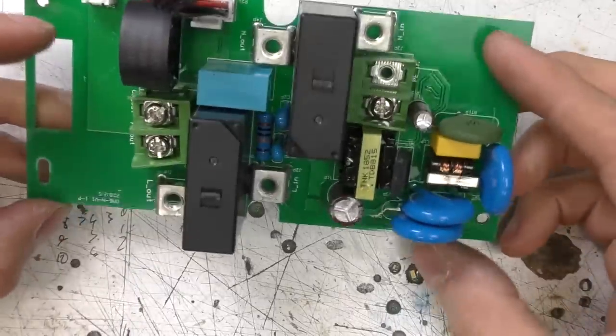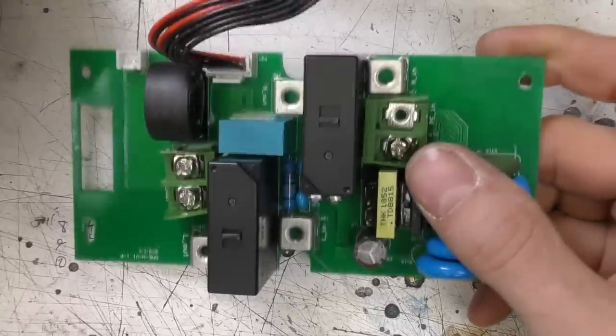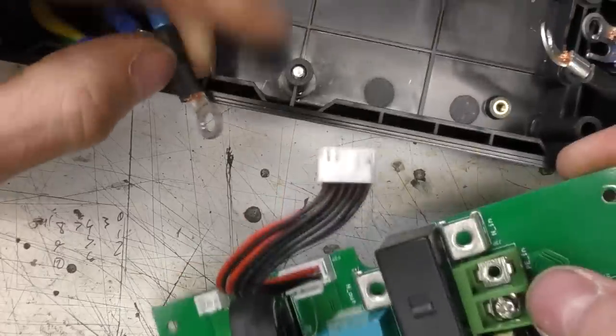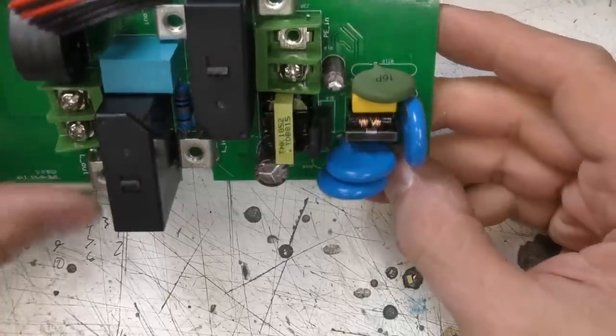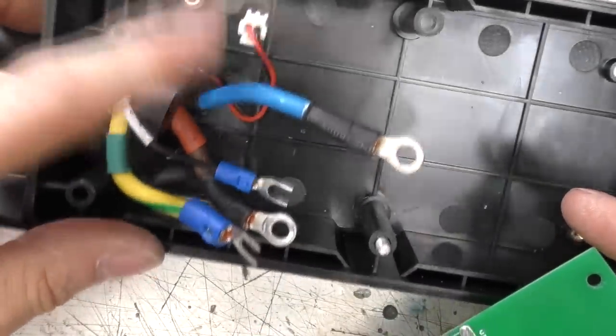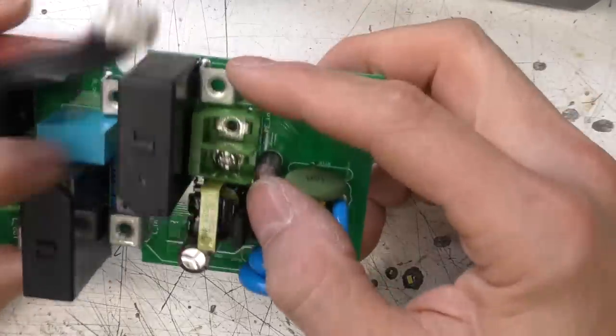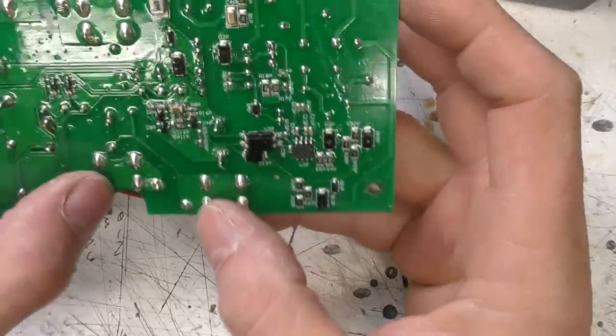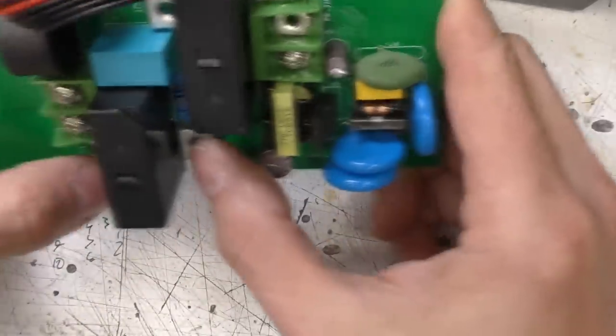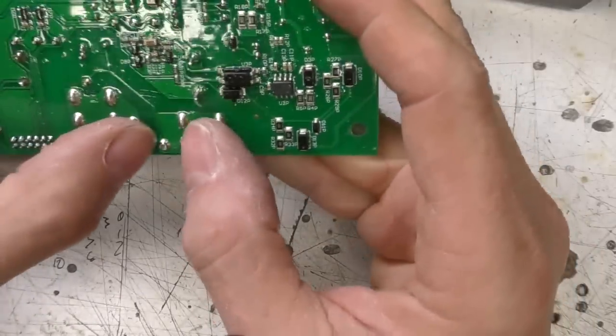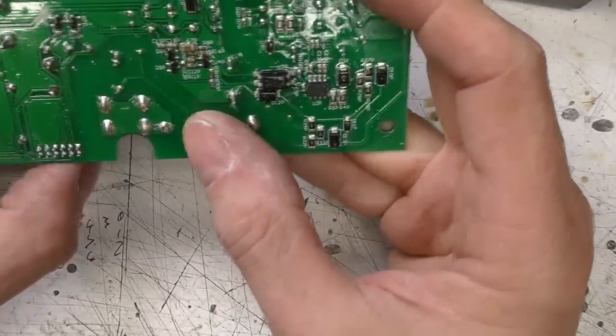So this board comes out much easier than the other unit. The neutral wire comes through that current transformer without taking the tag off, so that's much nicer. And so this board is pretty much just power components. The RCD current transformer is there off the PCB, it just plugs in. One thing that's quite notable on this is there's much shorter tracks carrying the main current. Both the live and neutral in and out connectors are right next to the relay contact, so there's a very, very small amount of track, so that just reduces the potential for PCB heating.